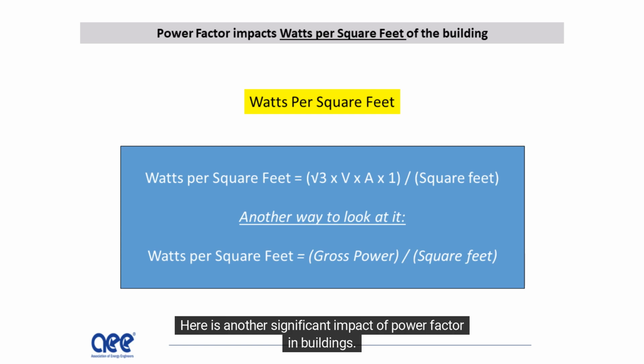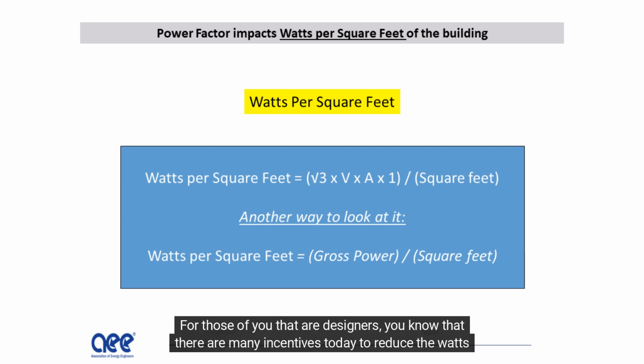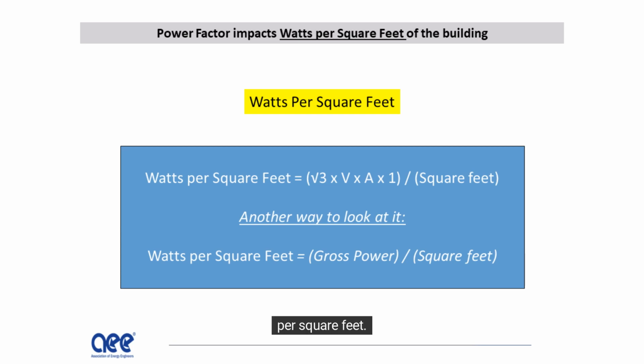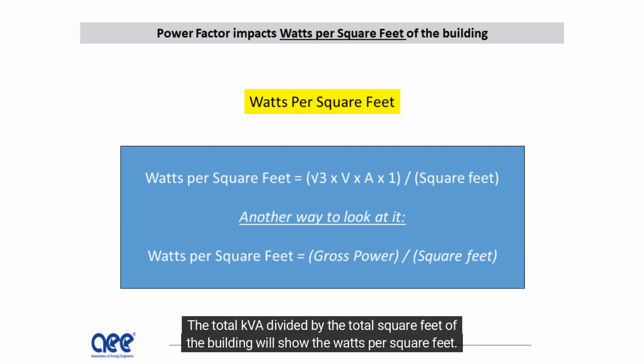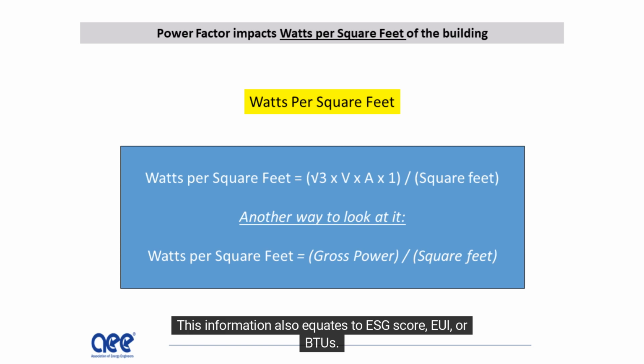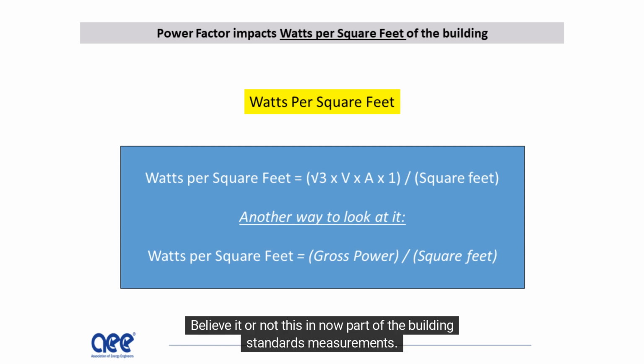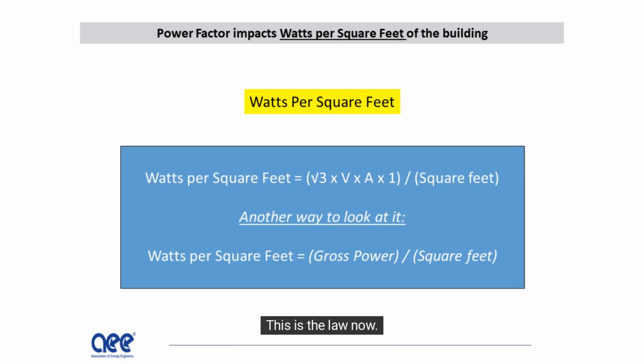Here is another significant impact of power factor in buildings. For those of you that are designers, you know that there are many incentives today to reduce the watts per square feet. The total kVA divided by the total square feet of the building will show the watts per square feet. This information also equates to ESG score, EUI, or BTUs. Believe it or not, this is now part of the building standards measurements. Buildings that don't meet the established scores will be penalized heavily. This is the law now.